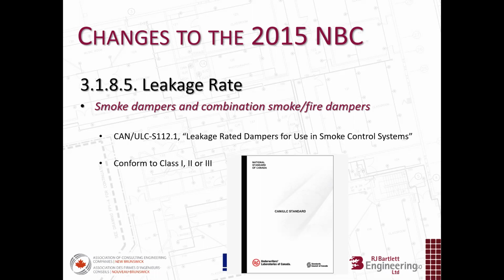Okay, and one other question not related to fire dampers. Sure. Are there any fire resistant coatings acceptable to protect foamed plastic in lieu of the barriers noted? Coatings in the sense of intumescent products, I'm thinking like spray coatings and things. So with that, my understanding is that the ones that have been listed, from what I've seen, are all listed to rate non-combustible construction. So they can be spray applied, and they do provide a fire resistance rating, but only to non-combustible surfaces.